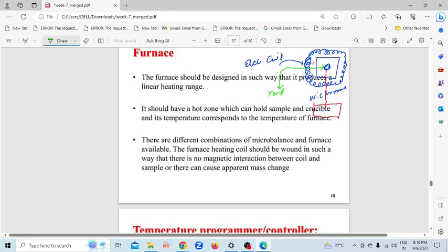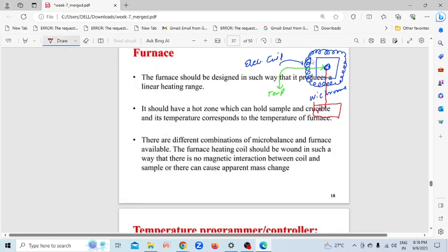Initially, by this electric coil you are heating your sample. It will decompose, and the temperature will be measured by this green colored thermocouple, and the mass change will be measured by this balance. Okay, so is everything clear? This is the complete working principle of your TG.